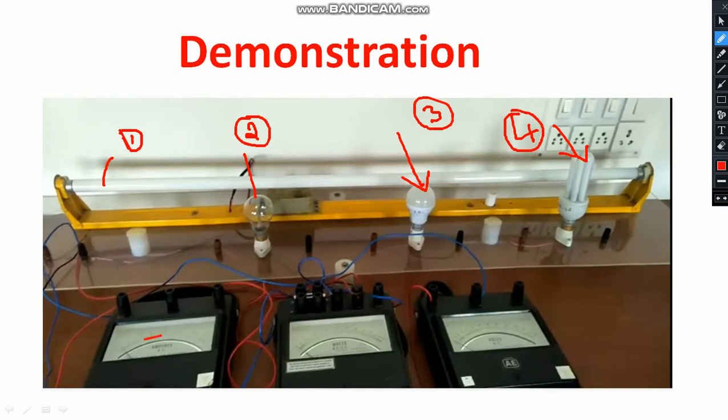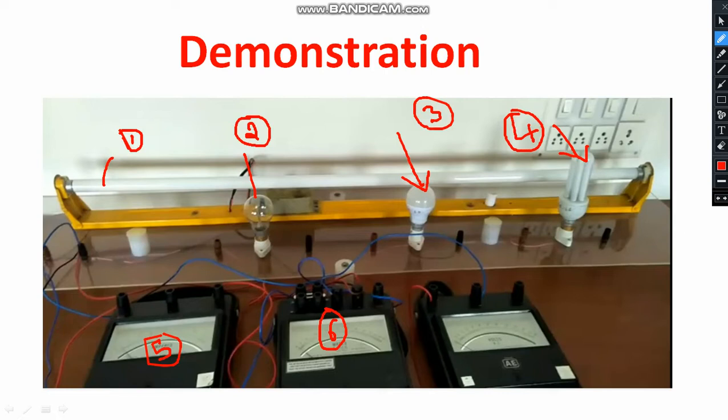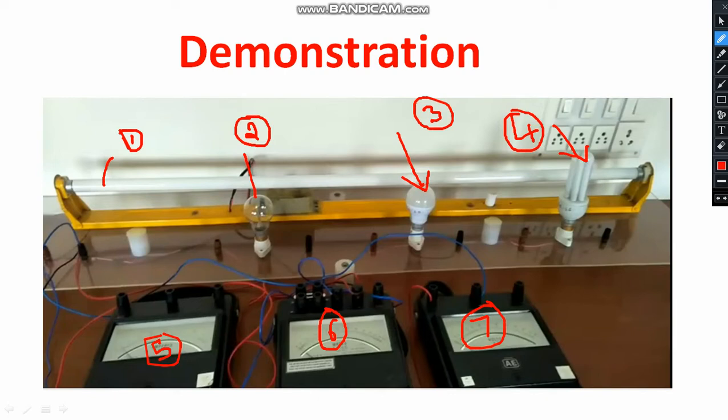We have the meters. You can see the ammeter, component 5. Component 6, we are having the wattmeter for the measurement of real power. And we have the voltmeter, seventh one, to measure the voltage across the lamp. Here I can use multimeter also. Set the multimeter. Don't forget to set the multimeter into AC mode. This is actually the setup. We need the better quantity or better quality of fine connecting wires also required. Remember that for series connection I am supposed to use thick wire. 2.5 mm square diameter you can use. For parallel connection I am supposed to use thin wire. 1.5 mm square can be used. This is your experimental setup.